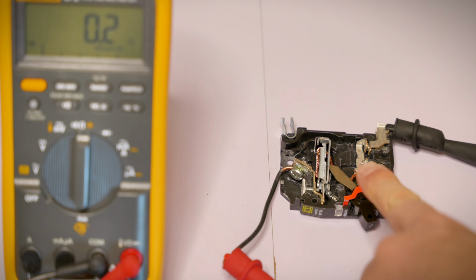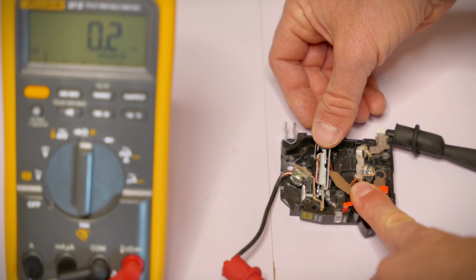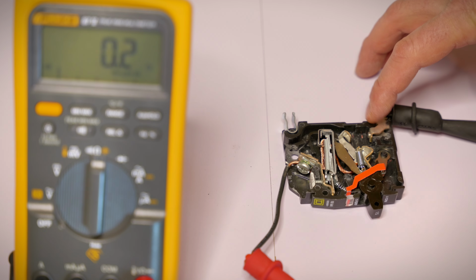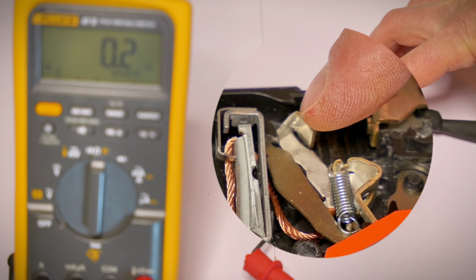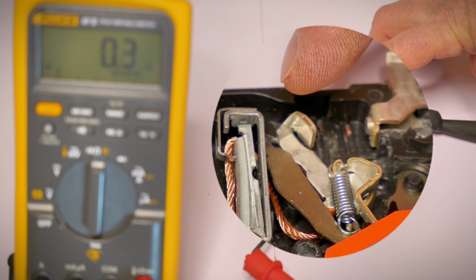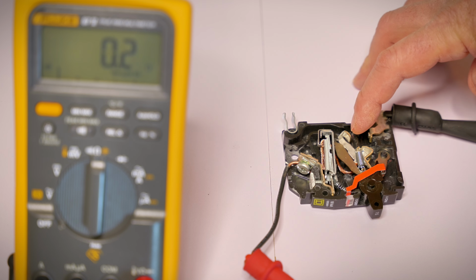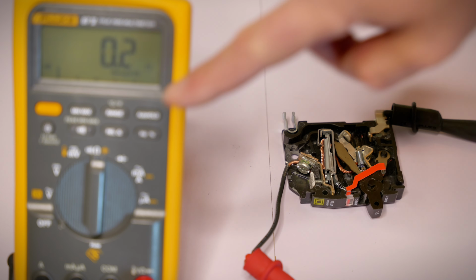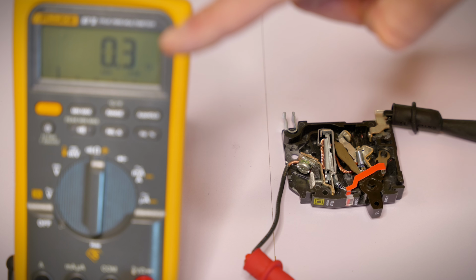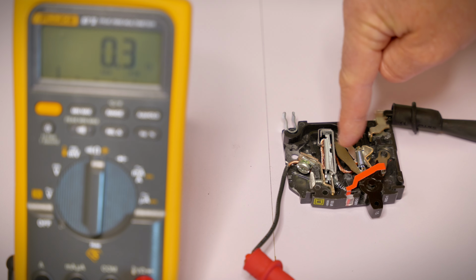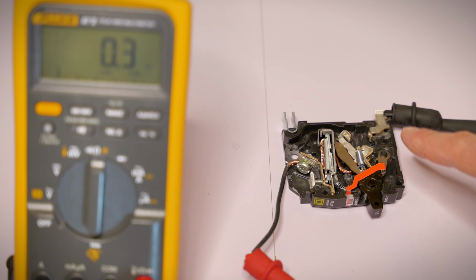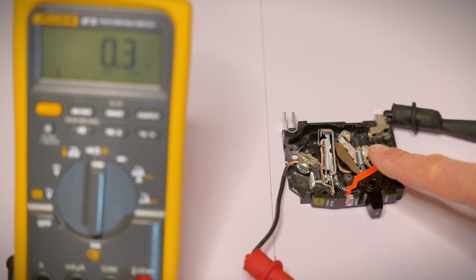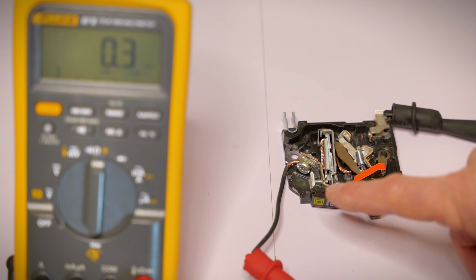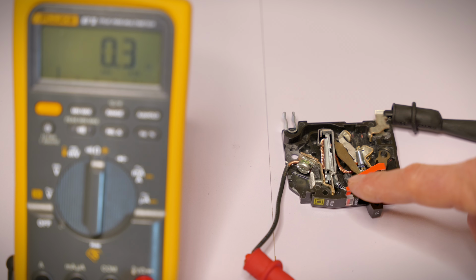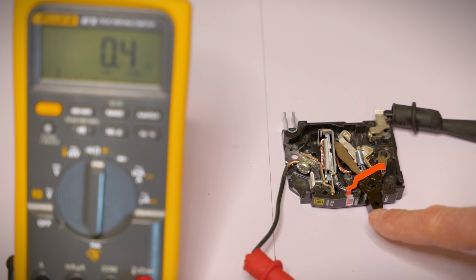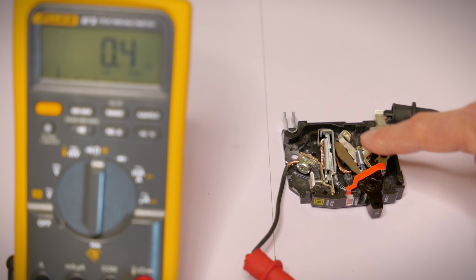Let's say that your circuit breaker has overloaded and tripped. And you can see that the moving contact is actually not in contact anymore. So the circuit breaker has tripped, but as you can hear and see, we are still getting continuity across the circuit breaker somehow. So what that means is somewhere internally inside that circuit breaker, you've got another connection that's an inadvertent connection. Even though it's tripped in the off position, you have your orange flag, it's still making continuity.